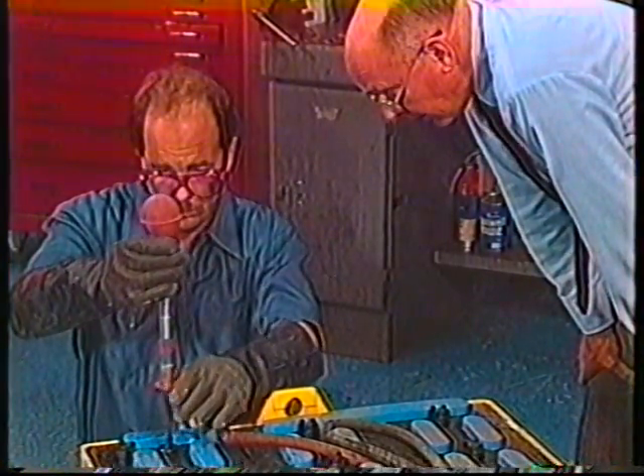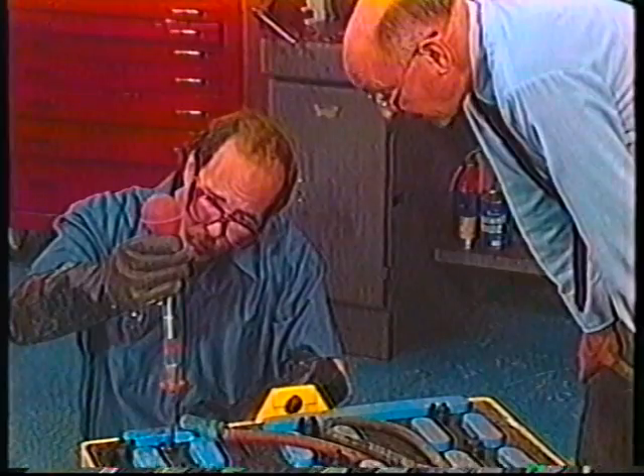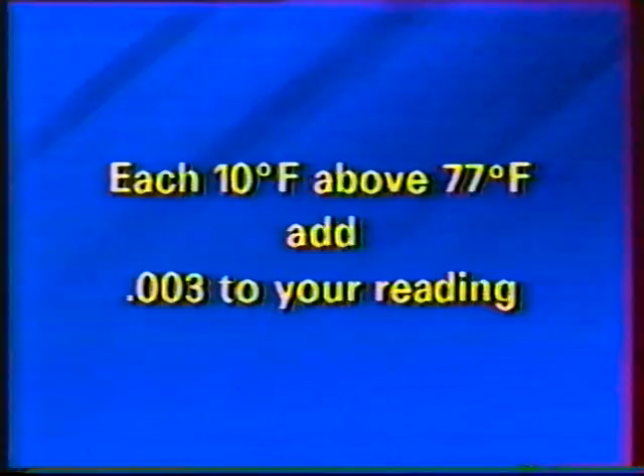Temperature affects the specific gravity of the electrolyte, so you have to measure the electrolyte temperature after measuring the specific gravity. For each 10 degrees above 77 degrees that the electrolyte reads, you add 0.003 to the hydrometer reading.